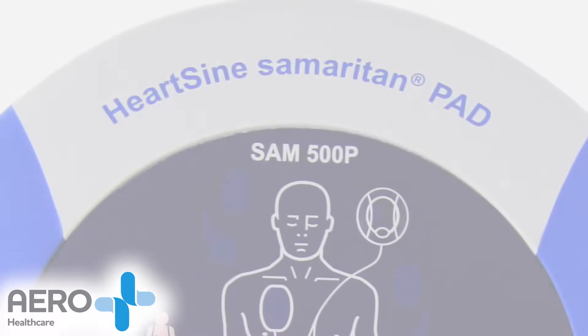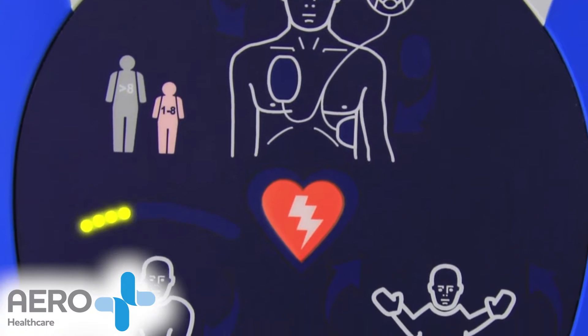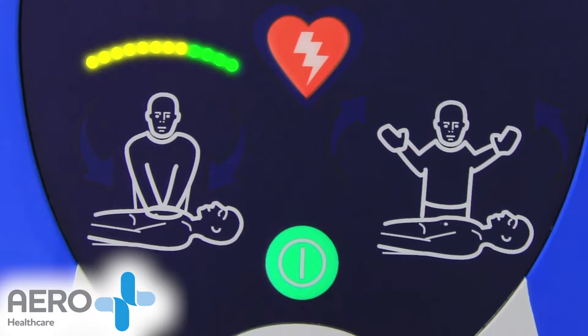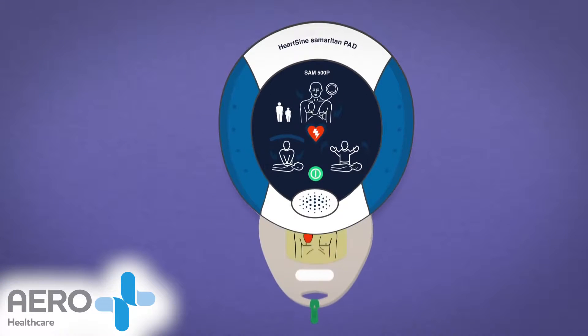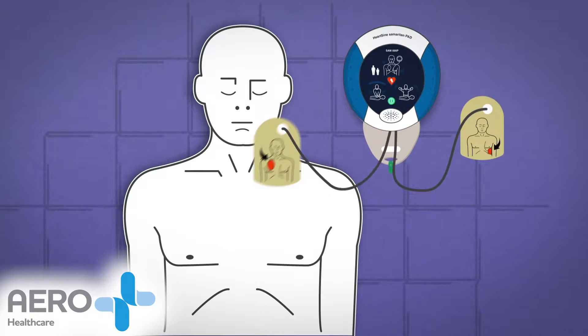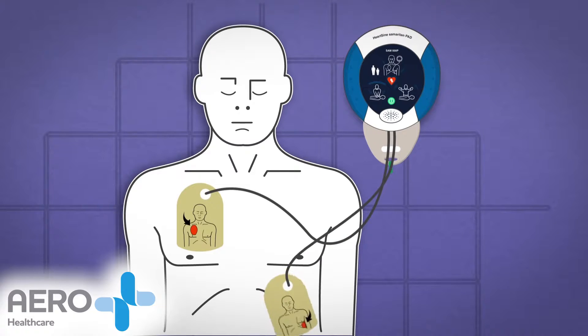HeartSine's CPR Advisor provides real-time visible and audible feedback to the rescuer on the quality of CPR compressions during a sudden cardiac arrest. HeartSine's patented CPR Advisor uses only the defibrillator electrodes to detect changes in patient impedance, rather than accelerometers commonly used in other AED solutions.